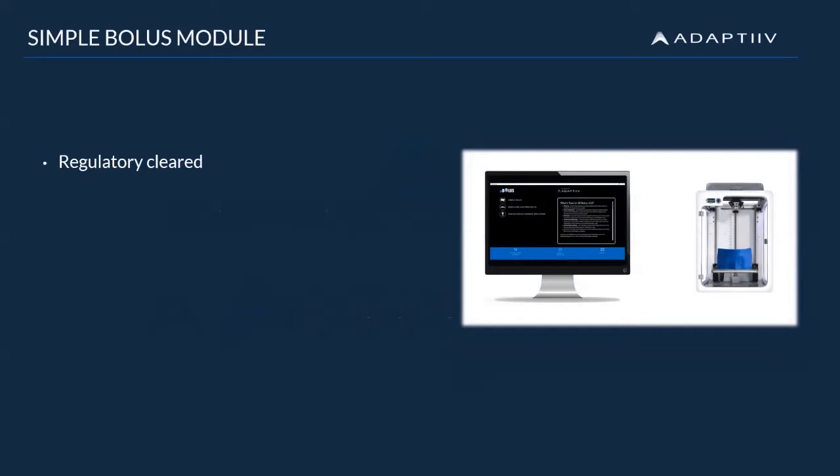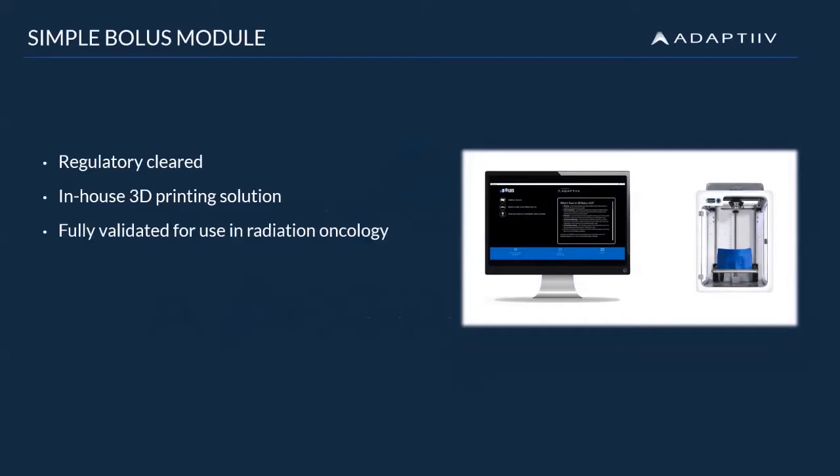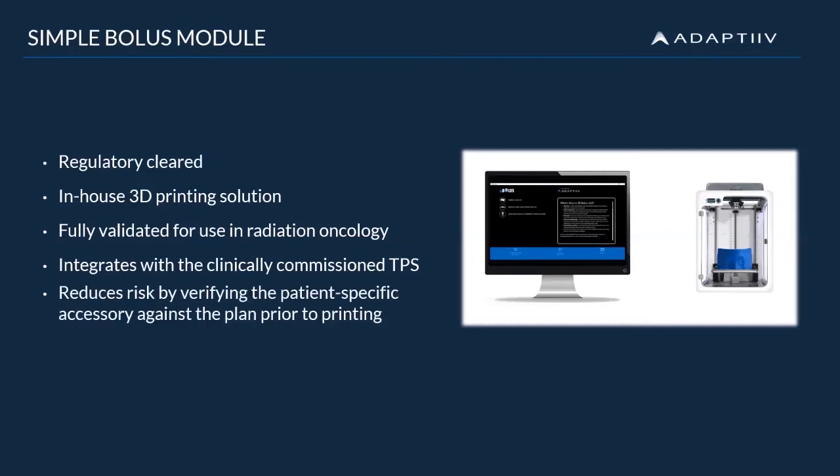We provide cancer centers with an in-house solution complete with software, 3D printer, and filament materials, all of which have been fully validated for use in radiation oncology. A major benefit of Adaptiiv software is the integration with the clinically commissioned TPS. This allows you to import the patient-specific bolus designed in our software back into your TPS for verification against the initial treatment plan that was created. This reduces risk and ensures that the bolus being printed matches the bolus in the TPS plan.